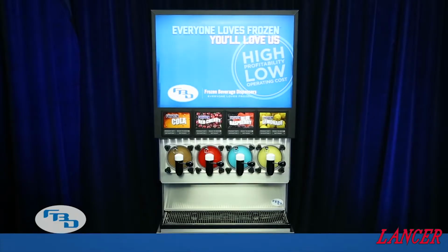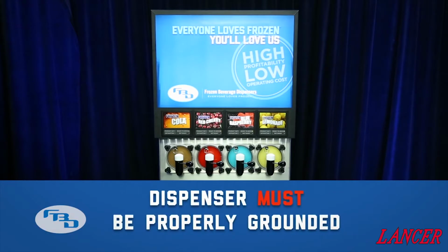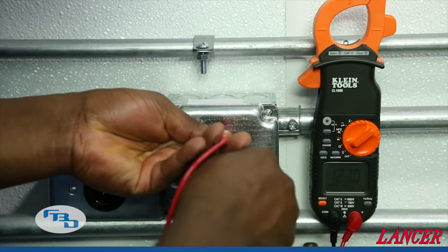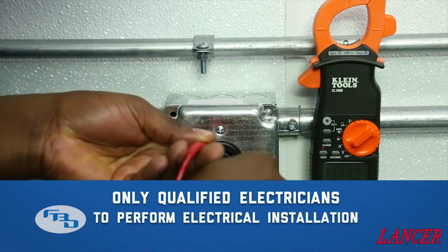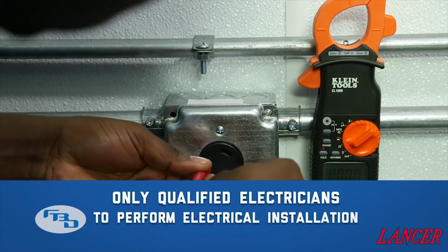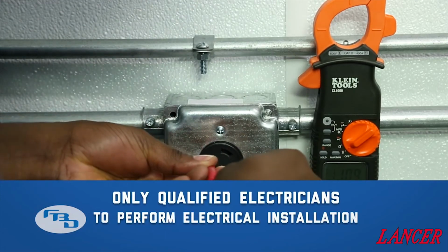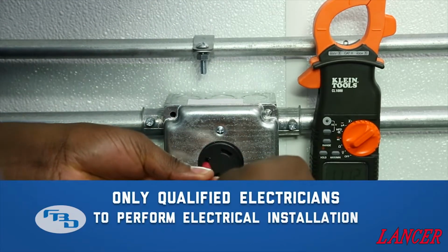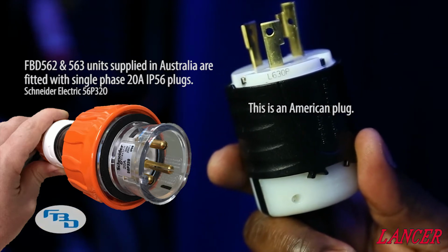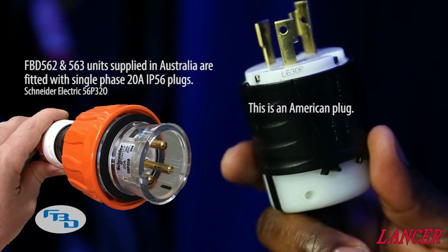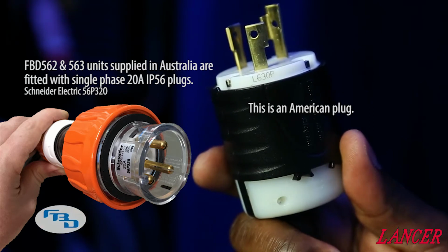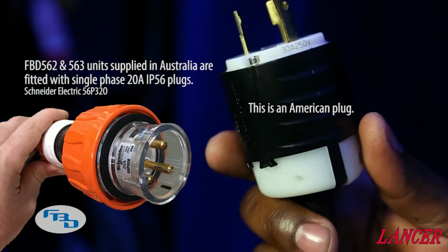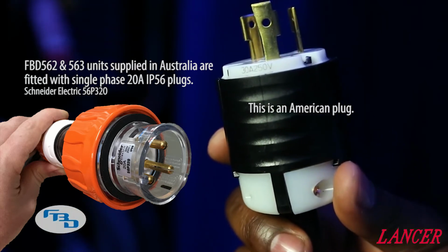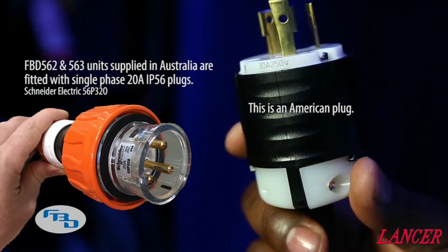The unit must be properly grounded to avoid possible fatal electrocution or serious injury to the installers and to the operator after installation. Only qualified electricians should perform the electrical installation, and the work must meet all applicable state and city codes. The power cord is provided with a 3-pronged grounded plug. If a 3-hole grounded electrical outlet is not available, you must use an approved method to properly ground the unit.